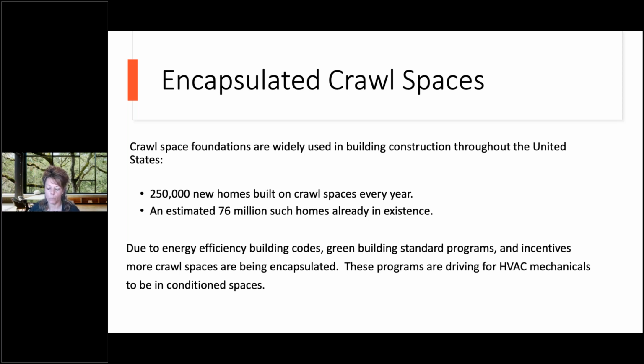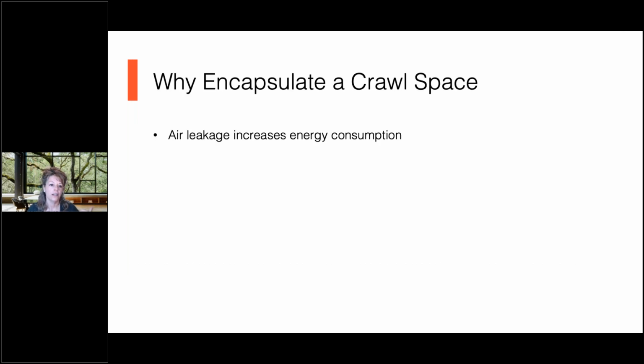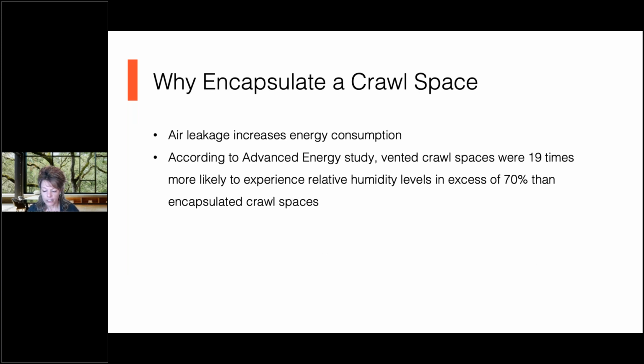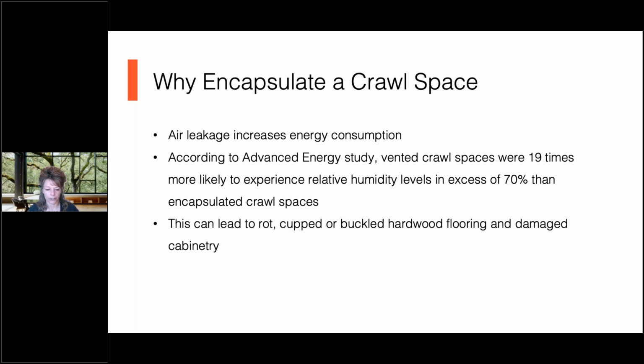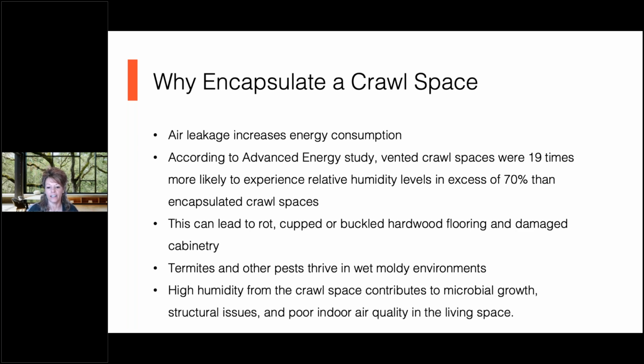And I think that we're going to see that more and more, just because we know the amount of air leakage from our systems that is very energy inefficient. So we're going to be seeing our attics and our crawl spaces conditioned much more as part of our building standard programs. So you encapsulate it because of air leakage. You can reduce the RH in these spaces when they're encapsulated. A lot less rot. We can protect the homes a lot better. Termites and other pests cannot thrive in these conditions. And high humidity from the crawl space contributes to microbial growth, structural issues, and poor indoor air quality, because 50% of the air below the home is making its way into the living space.